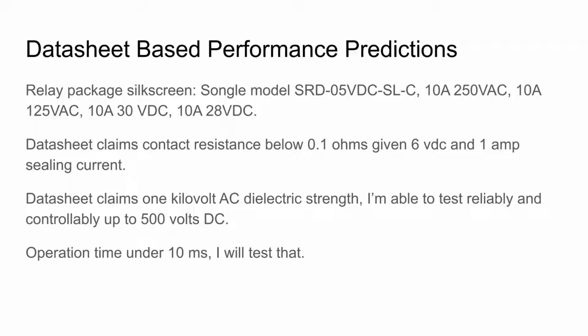The datasheet claims 1,000 volts AC dielectric strength. I'm willing to test that up to 500 volts using an insulation tester. My tester always overvoltages a little in actual operation, so sending it to a kilovolt would test to at least a kilovolt plus 1/10, maybe more, which proves nothing if it fails. If it's good up to 500, it's probably good.